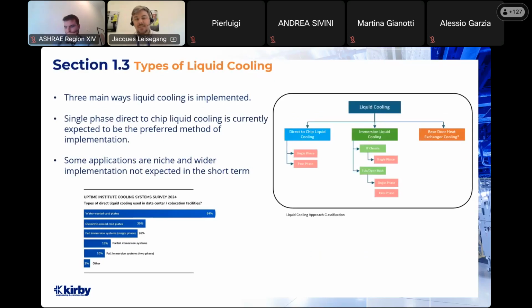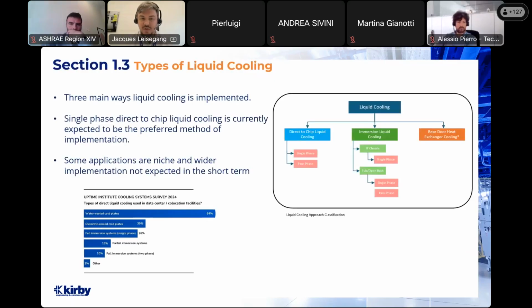So there's different types of liquid cooling. Liquid cooling isn't just liquid cooling, and it's not the same across the board. There are three main ways in which liquid cooling is implemented. Firstly, we have direct chip. You have immersion cooling, and not strictly liquid cooling, but you also have a rear door heat exchanger, which definitely increases the rack density that you're able to manage. So within direct chip liquid cooling, you can either have a single phase or a 2-phase liquid cooling.